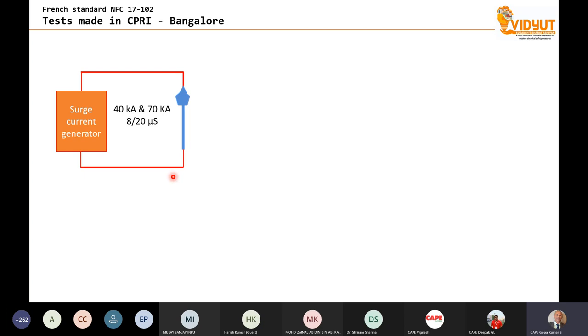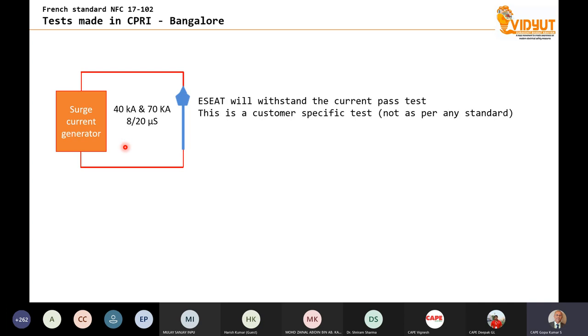Whereas in India, there is a surge current generator. There are two generators. One is 40 kiloampere and one is 70 kiloampere. The generators are connected directly to the ESE rod, and maybe 3 pulse, 4 pulse, 5 pulse, 2 negative, 1 positive, 2 positive, 2 negative. A few pulses are given. And finally, the CPRI gives a certificate. And you must understand that this is not a test made from a standard. This is a customer-specific test.